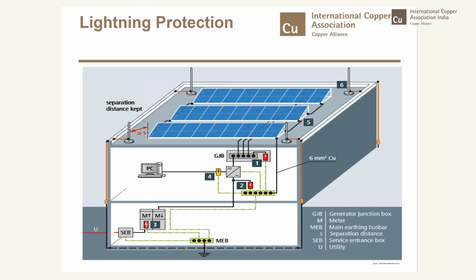So you can see the red cable which is coming down from the air termination, that is 6 square mm copper cable, and finally it is terminated to the master earthing junction box. So this is how a typical scheme is, but the number of electrodes, number of air termination rods, the height of the rods, etc., are purely dependent on the area of coverage given by the individual air termination rod, and those principles have to be applied for arriving at these quantities.